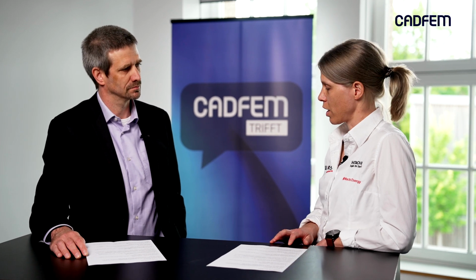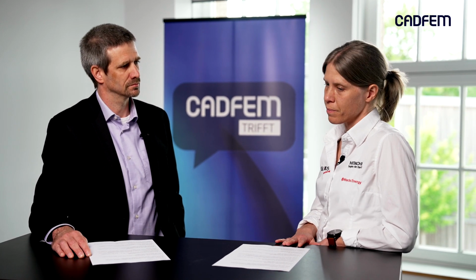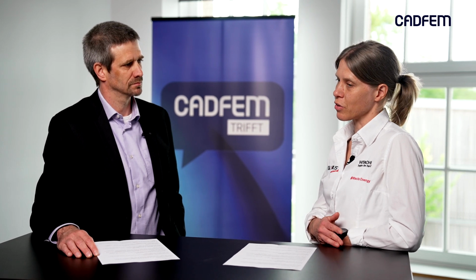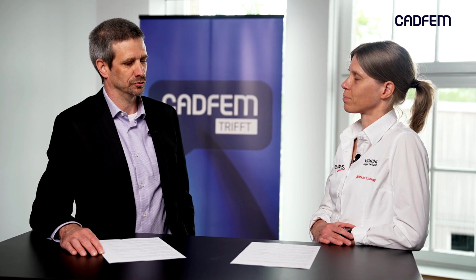So these are things that exist for each and every transformer, and because we have designed quite many transformers over the years, we can also validate our new workflows against existing designs and the measurements. Okay, so also comparing simulations, calculations and measurements. Yes, exactly. This is also an important point, that we sometimes need to calibrate something. We see some tendencies that simulations predict higher losses, so we can calibrate them, things like that.